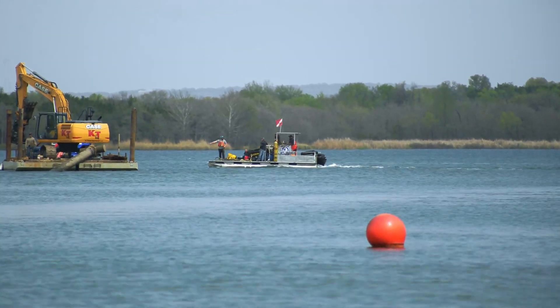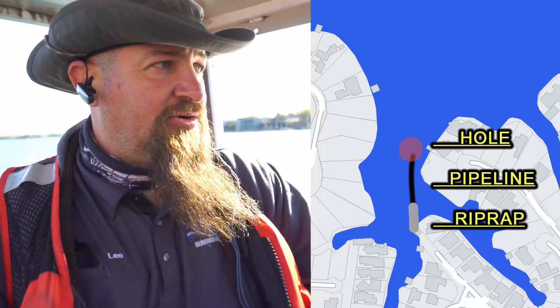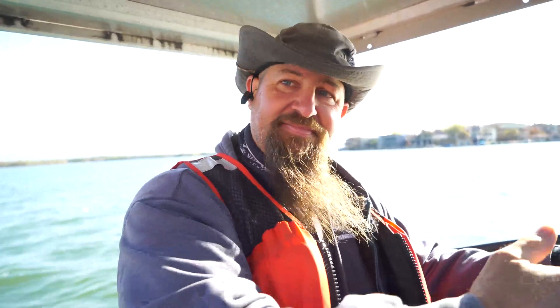As he was inspecting along it, he was actually walking beside the pipeline and went to fall into a hole. When he fell into the hole, he got back up and grabbed the pipeline again and discovered the flange was there at the hole. As he was inspecting the flange itself, he was able to actually stick his hands in between the two flanges, which had an opening — creating a void where, whenever they were sucking water, it was actually drawing from that connection because there were only two bolts actually holding the pipeline.